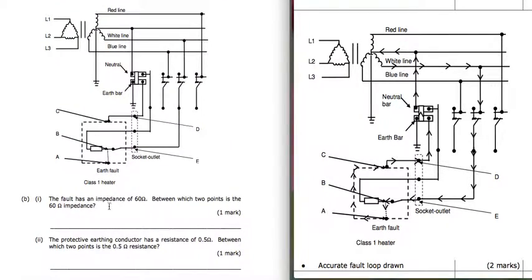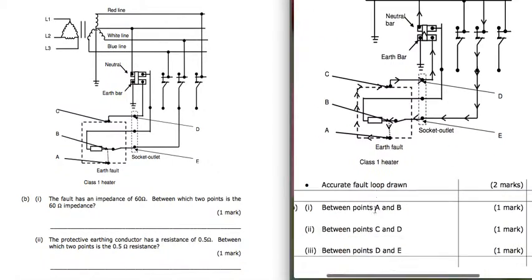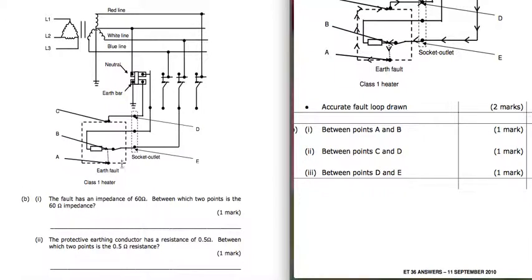The fault has an impedance of 60 ohms. Between which 2 points is the 60 ohms impedance? So the 60 ohms is that fault there, so it's between A and B. The protective earth conductor has a resistance of 0.5, so where's that? So that's there, that's between C and D.